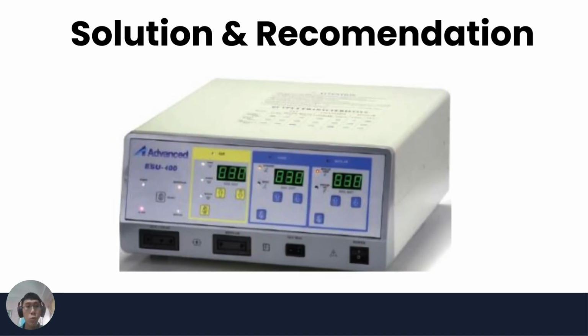Solution and recommendation. The ESU should have a solid-state generator operating within a frequency range of 300 to 1000 kHz. It should feature isolated monopolar and bipolar outputs and be equipped with hand or foot switches. For general operating room use, the maximum power output for monopolar cutting should be 300 watts and an open circuit voltage ranging between 200 and 1200 peak volts.